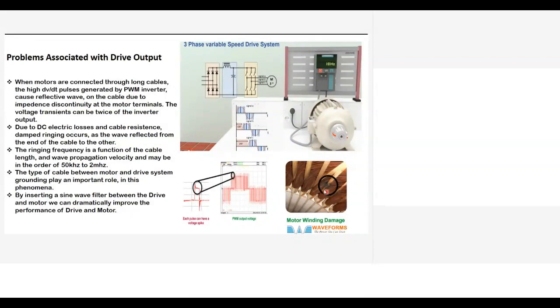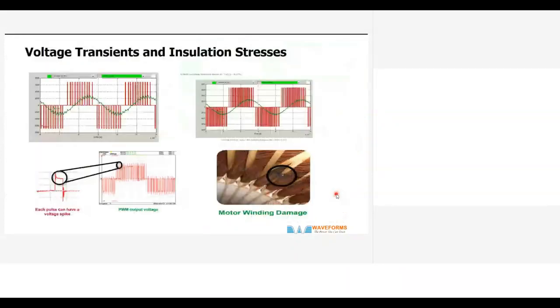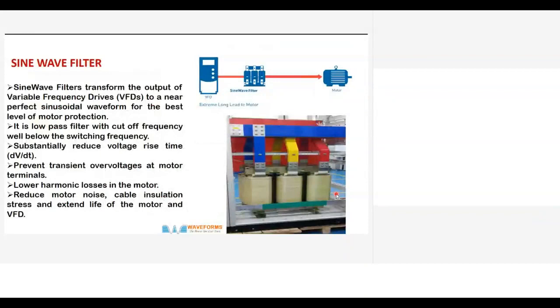By inserting a sine wave filter between the drive and the motor, we can dramatically improve the performance of the drive and the motor. There are many cases where people are still not aware that the output of the drive is a square wave and not a sine wave. So the sine wave filter converts this square wave into a sine wave. It is basically an LC filter, which will convert this high frequency square wave pulse into a sine wave. Thereby it eliminates all the transients that are generated by the long distance cable and the motor itself.